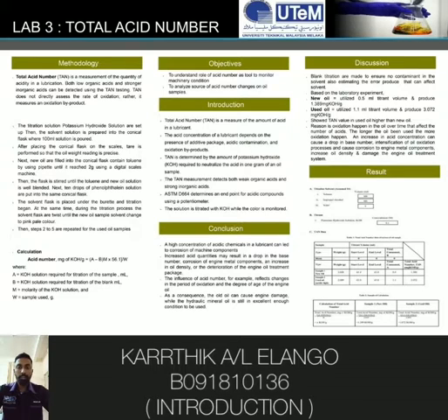Acid substances, when reacting with metals, form salts, which are responsible for the formation of sludge in the lubricating oil. An increase in acid number causes a decrease in base number, and it also causes an increase in oil density or depletion of the engine oil treatment package.